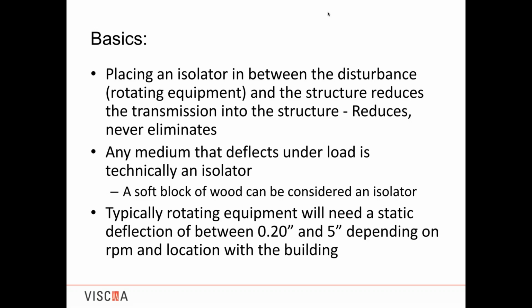Though the rotating equipment we typically deal with in HVAC and power generation, you'll hear discussions about inches of deflection and static deflection. And typically for it to be effective, we're looking roughly between 0.2 inches and 5 inches of static deflection. Later on, Angela will get into some of these definitions, but right now we're talking about static deflection of the medium that you're using as an isolator with the static load of the equipment on top of it.